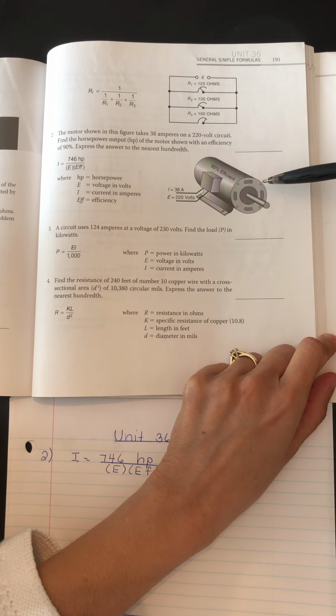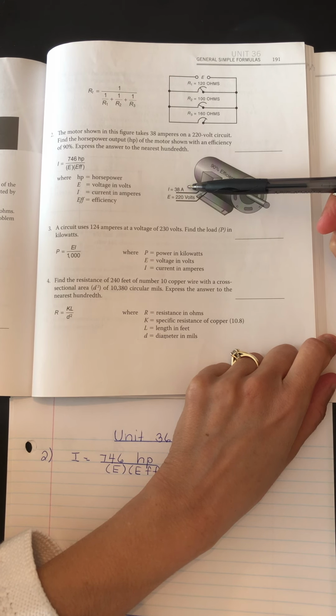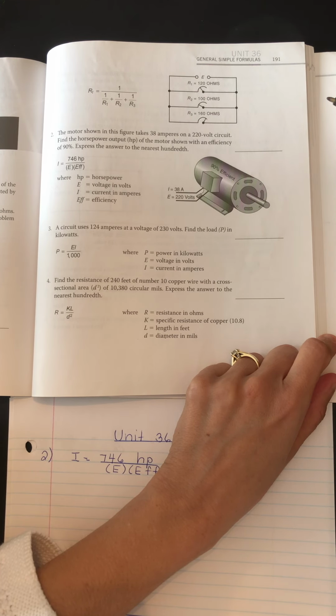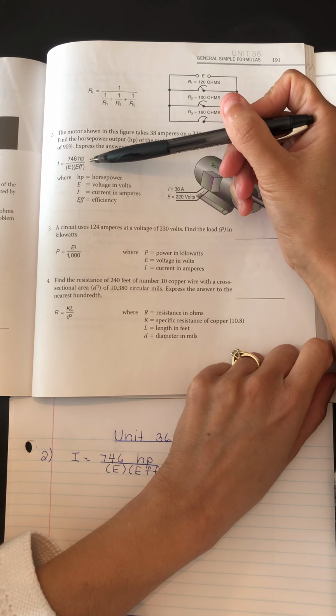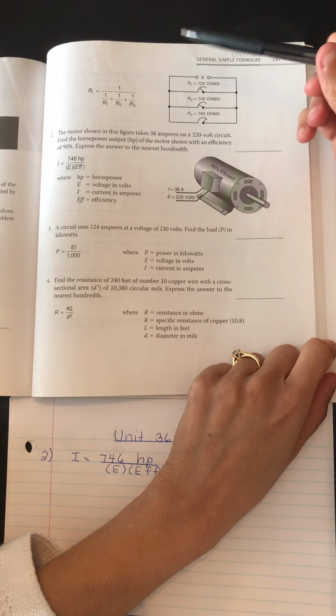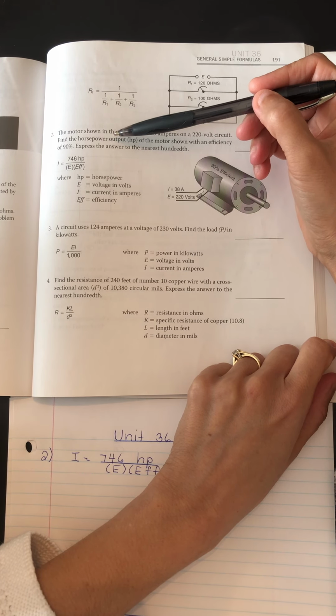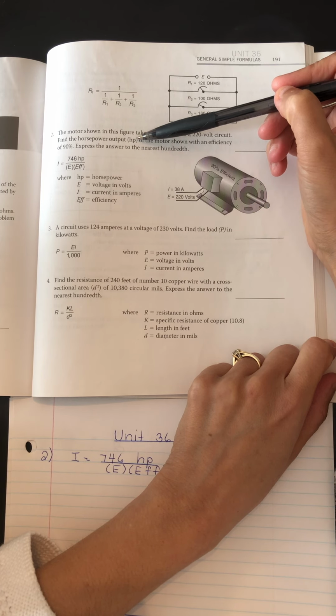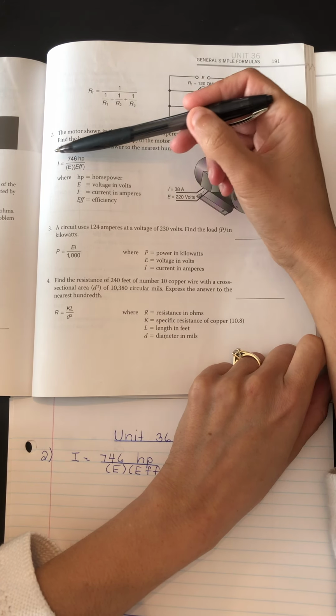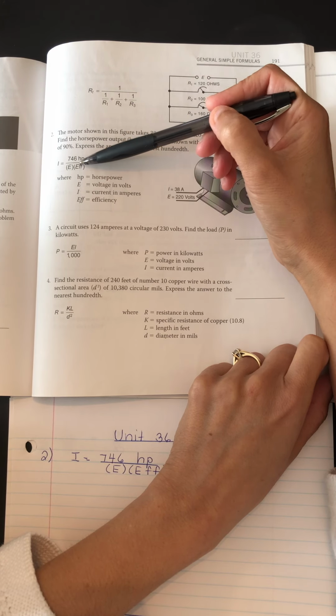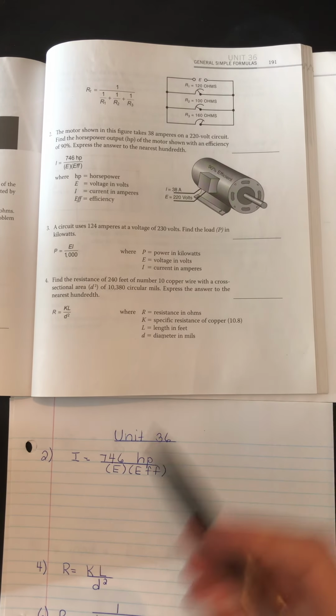It says the motor shown takes 38 amperes on a 220 volt circuit. Find the horsepower output of the motor shown with an efficiency of 90%. So that's the motor's efficiency. Express the answer to the nearest hundredth. And the formula for current is given here. So we're actually trying to solve for the power output in horsepower. So what we should do is probably take the given equation and isolate HP in that equation. So I've written it here.